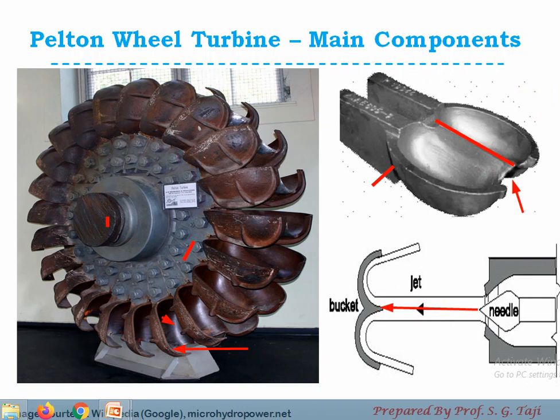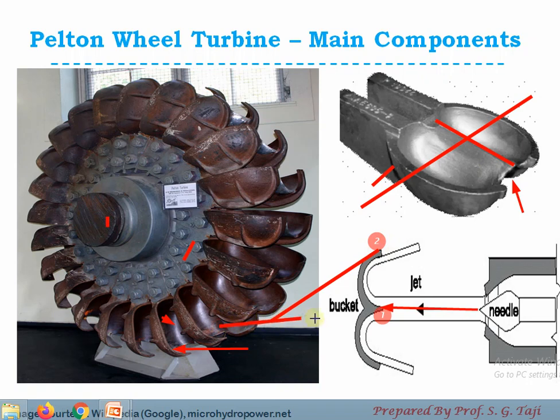Taking a cross-section of the bucket, the jet of water comes horizontally and strikes at the splitter. After striking, it gets divided into two halves, and both halves follow the contour of the bucket and get deflected at the outlet point. The first point where the jet strikes is the inlet point, and the point from where the jet comes out is the outlet point. The angle of the bucket at inlet is the inlet tip angle, and the angle at the outlet point is the outlet tip angle — both measured with respect to the direction of motion.